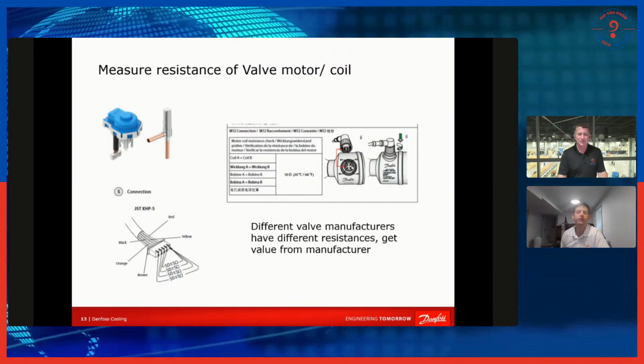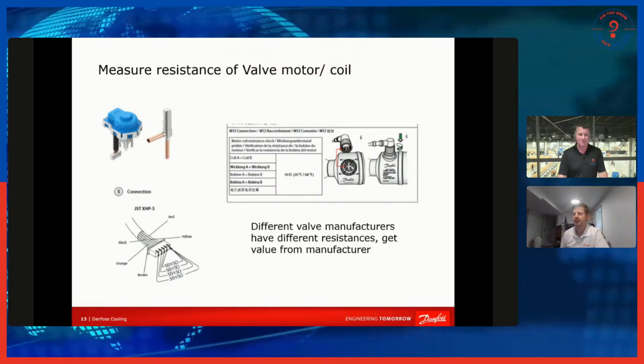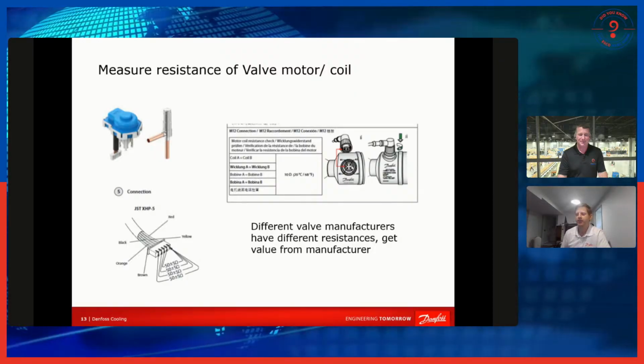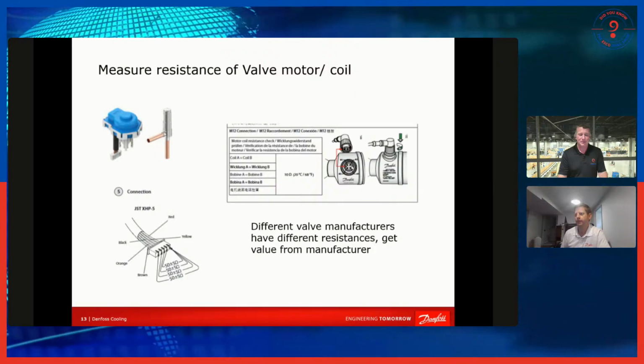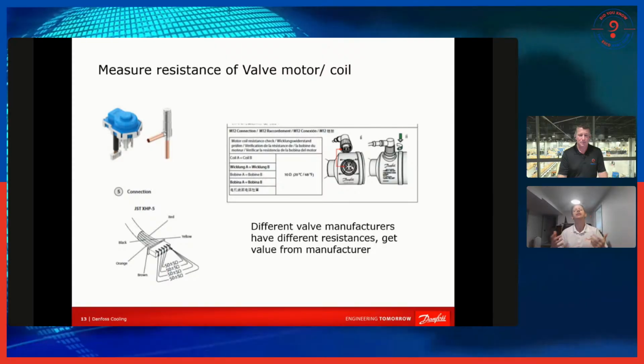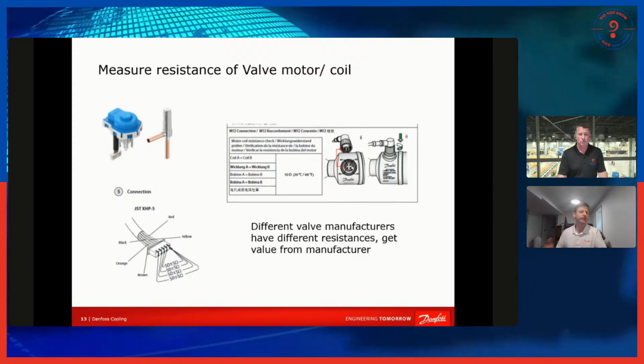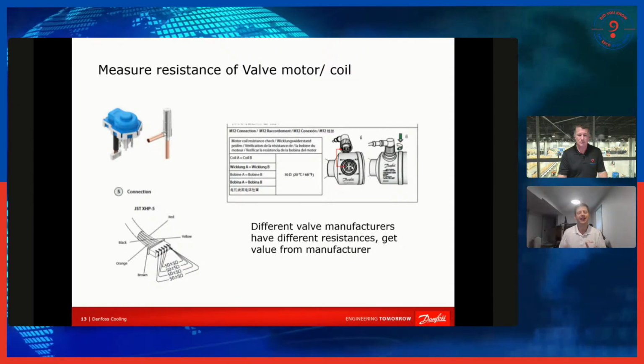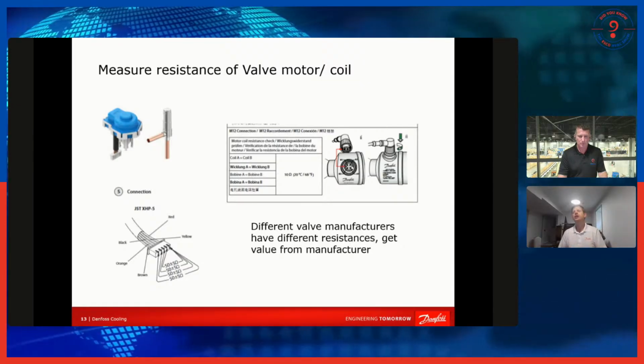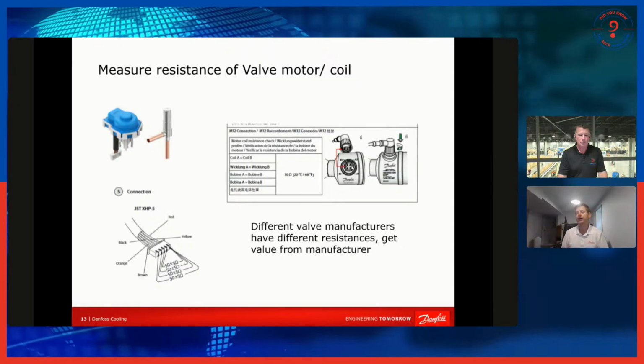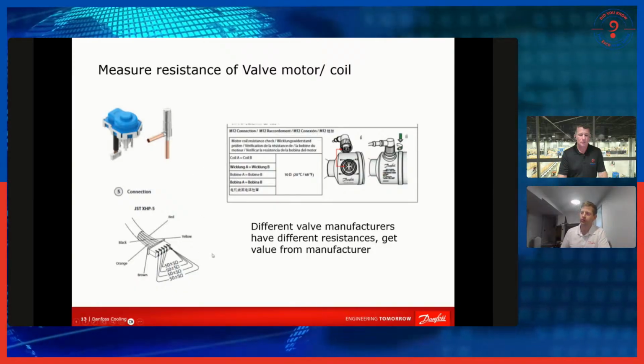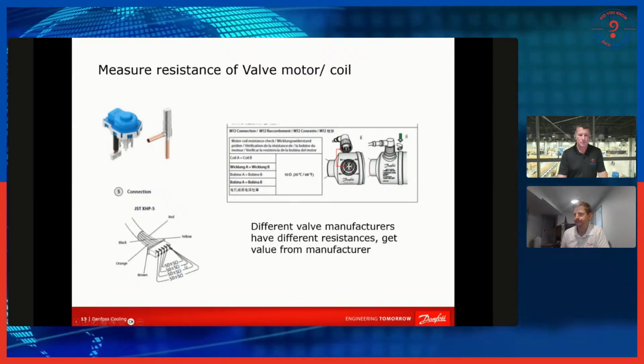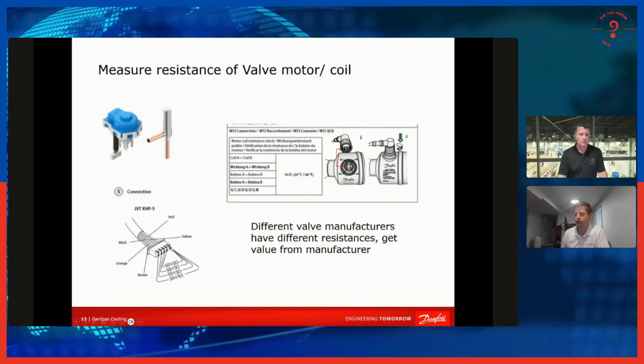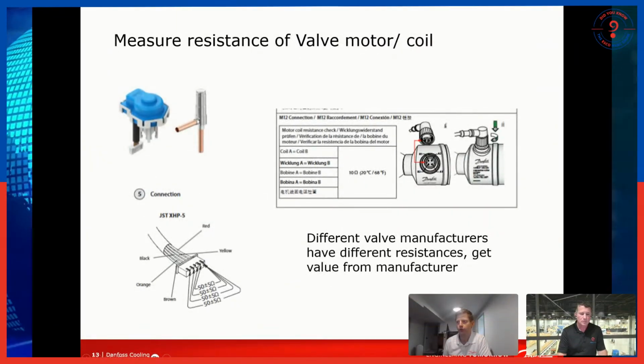So for the purposes of this slide, since I'm getting into troubleshooting, the goal is to try and eliminate, hey, does my stepper motor work? And one of the ways you can check, does my stepper motor work, or has it been damaged? Does it have an electrical burn to it? Is to ohm it out. And when it comes to the bipolar stepper motors, you compare everything to your neutral wire, and then you check, does it ohm out properly.